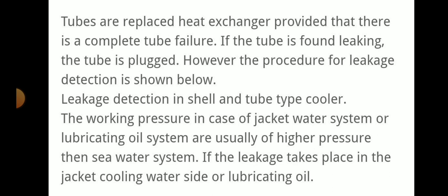The tubes are replaced by a heat exchanger provided that there is a complete tube failure. If the tube is found leaking, then the tube is to be plugged. If there is a leakage in the shell and tube exchanger, then the tube needs to be plugged. However, the procedure we are discussing here is leakage detection in a shell and tube type cooler.